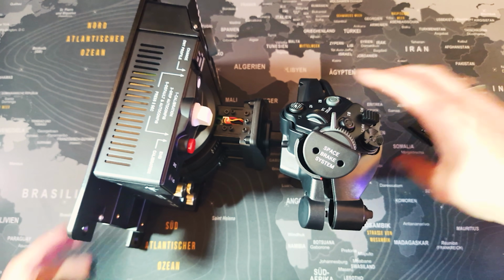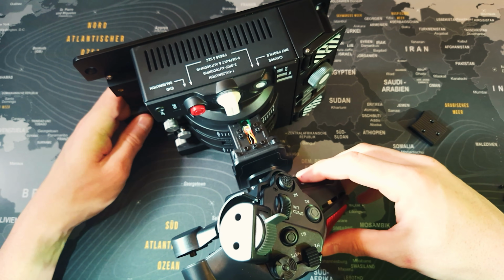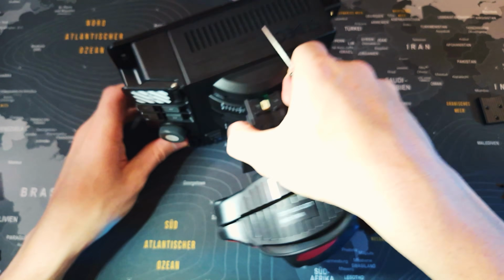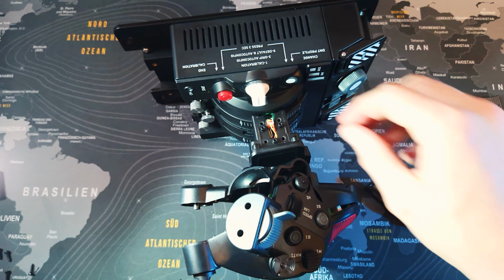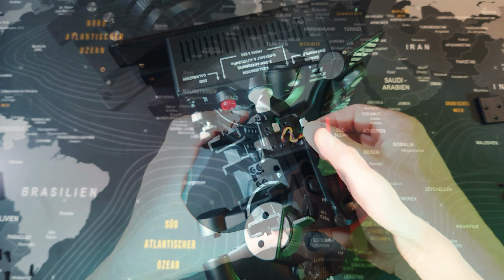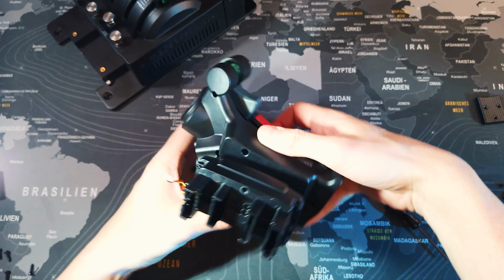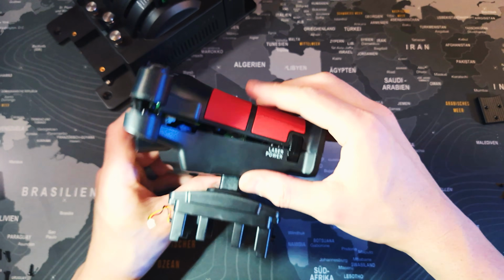Below are the actual screws that connect the handle to the base, which we also remove. When pulling off the connection cable, a little fingertip feeling is required not to damage it. Subsequently, we can then separate the handle, the grip, from the base.